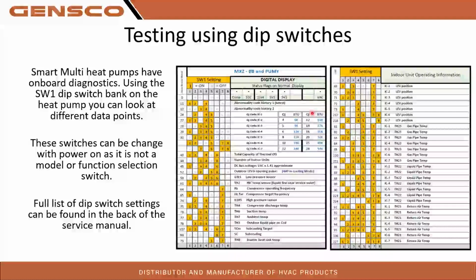If you have an active error code indoor, but it's not showing in the heat pump, use your SW1 switches. Start looking at your most recent error codes stored in the heat pump. With this, you can use those switches and look to see what all the error codes stored are. Just got to be careful because there's no timestamps associated with those, but you're looking at your most recent one. If you're having startup issues, obviously it's going to be the most current one there because you just started the system up. It hasn't been running for a couple of years.